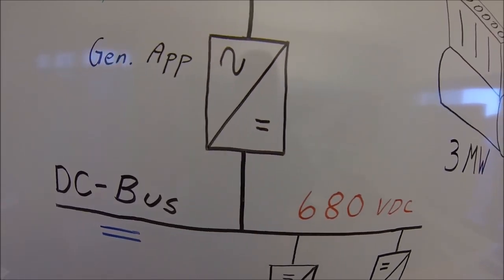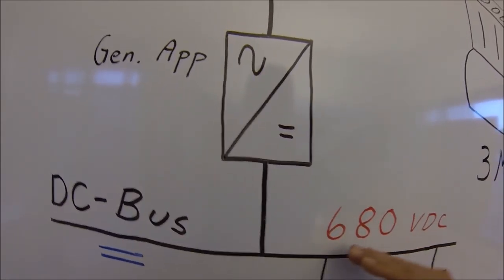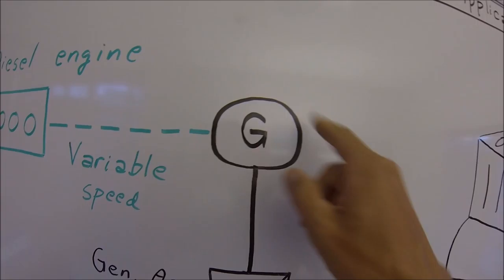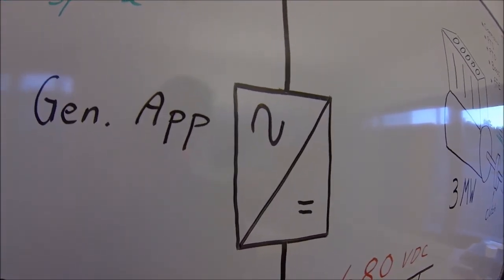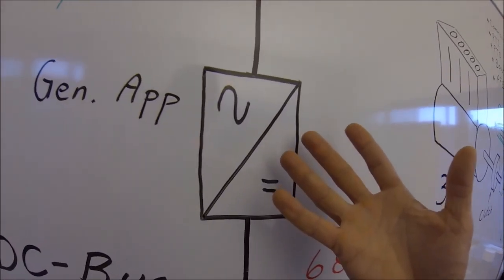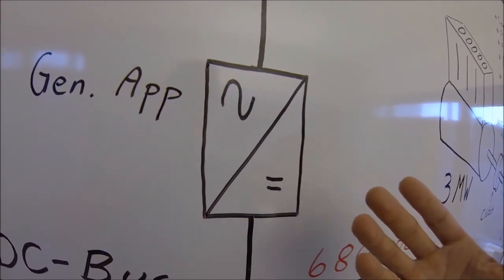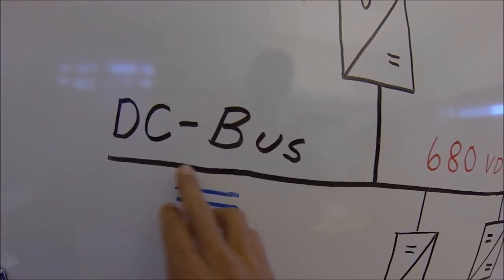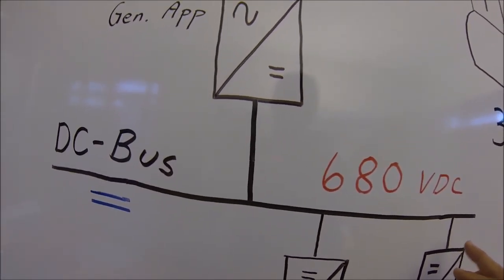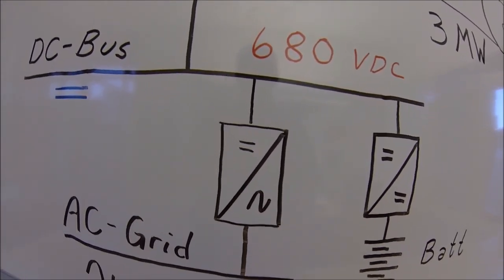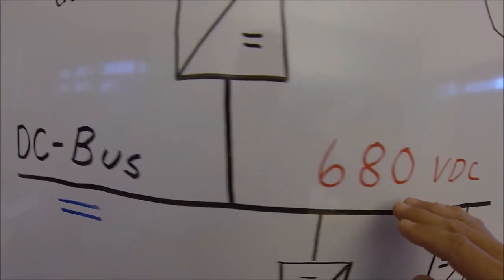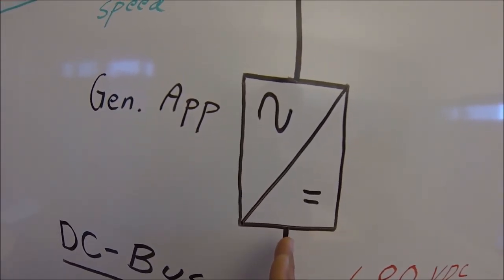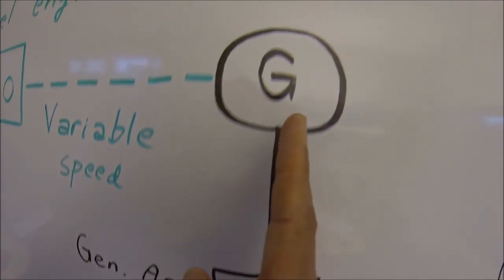The other mode is when we want to put power into the motor to drive a propeller or shaft. Then the generator application works more or less like a regular frequency converter, like the marine application. Then somebody else needs to produce the DC voltage on the bus, maybe an active frontend or grid application, or it could even be a battery. Then the energy will flow from the DC bus into the motor.